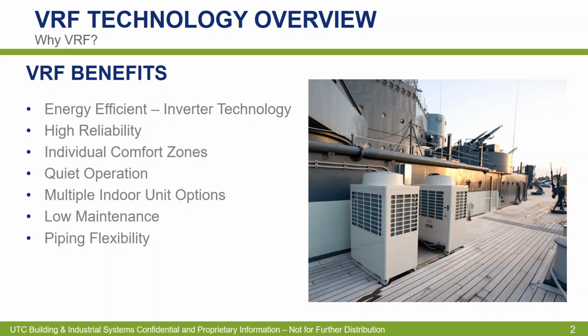Individual comfort zones and control. They are quiet, relatively speaking, to their counterparts, whether that be a large condensing unit or air-cooled chiller. They are quiet. Multiple indoor unit options. We all know the different fan coil types. Pretty much any fan coil type that we're used to on the hydronic side of things, we can do the exact same with VRF. Low maintenance and piping flexibility. Yes, these systems can handle a lot of pipe, but we do need to be careful. It's dependent on our application, right? What type of building we're trying to install the systems in. But we can get into that later on when it comes to more application-specific stuff.